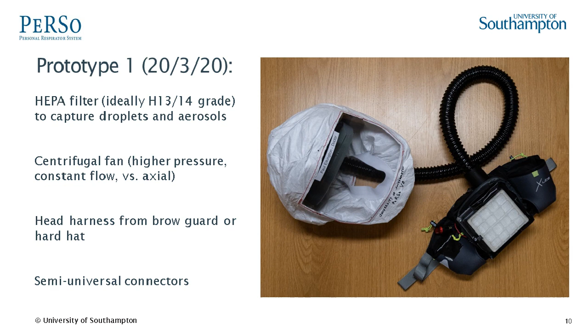The filter is matched with a centrifugal fan and a flexible pipe up to a headset. This is made from an adjustable head harness taken from a brow guard or a hard hat, and is covered with a hood, which in this case was sewn from Tyvek material obtained from a protective lab coat. We designed semi-universal 3D printed connectors so that components might be interchanged due to availability of different parts in different areas, or for different hoods. For example, different levels of protection might be required for different users. For example, people working on normal wards compared to anaesthetists who might be performing procedures which generate aerosols such as intubation of critical individuals. The assembly was worn in a runner's bag belt to be worn around the waist, weighed in total 1.4 kilograms.